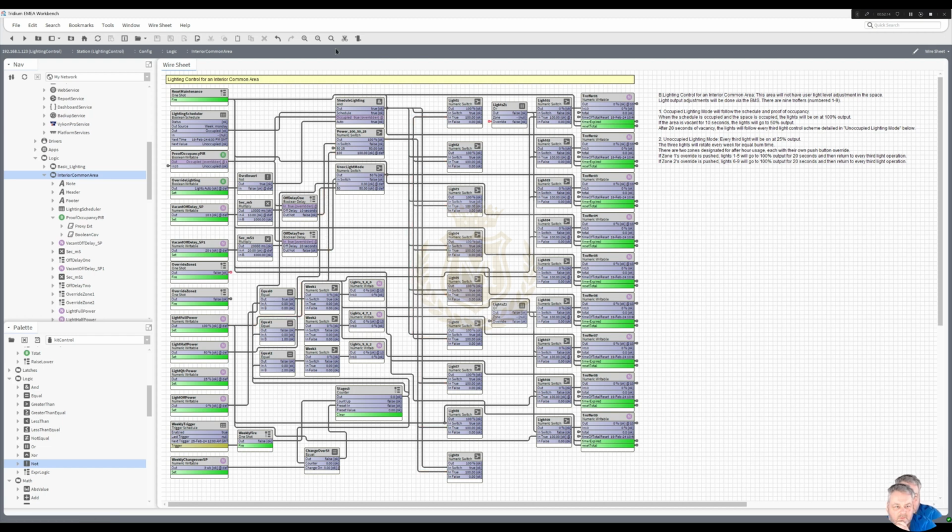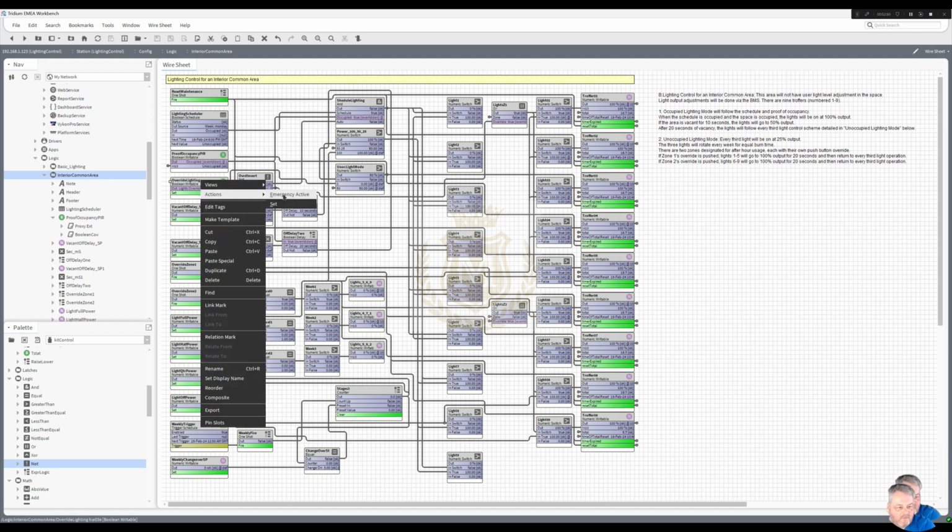I'm going to take this one out, and that one out, which goes to the override there. And I'm going to put it into override the zone, and override the zone there. And then I'm going to take my master override and put that into there, and put that into there. Now they're all off at the moment, but if I actually do my master override, they're all 100%, and I certainly don't want to do emergency active. I must have missed that one.